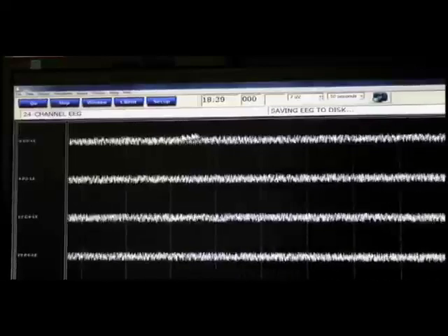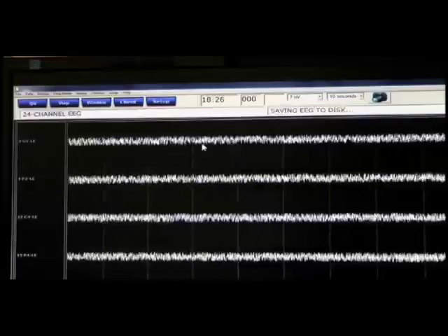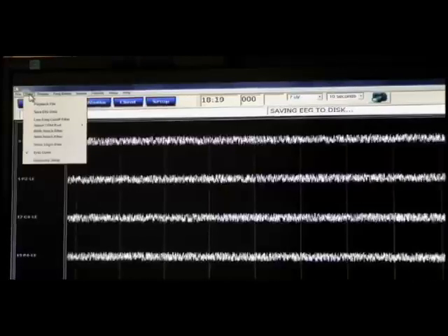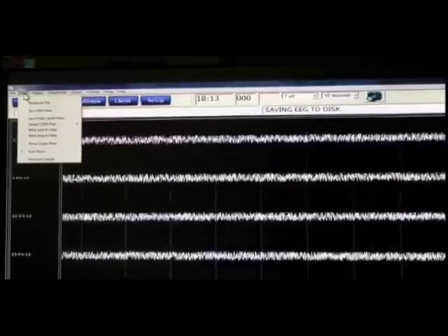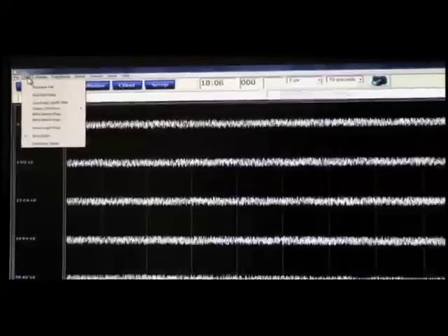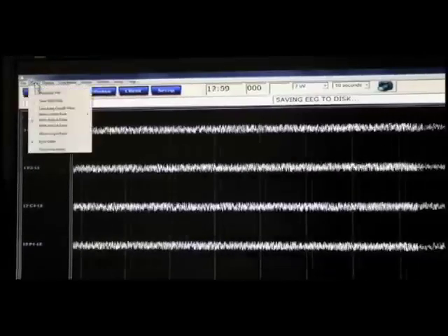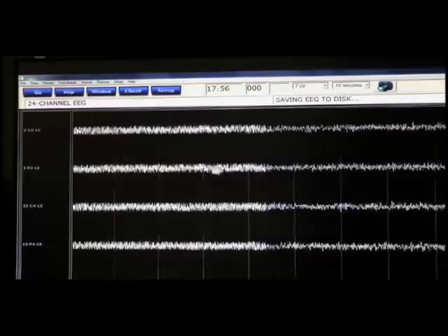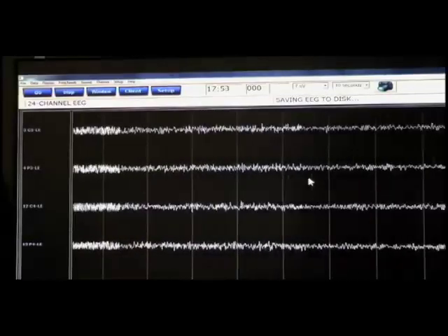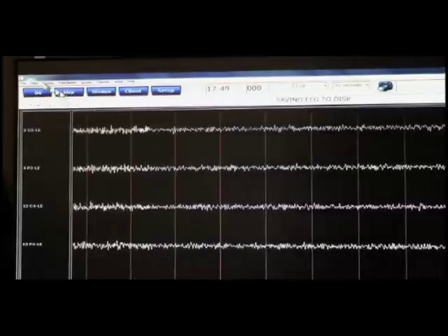When we have a signal like this, it's that typical garbage in, garbage out. So I would want to clean up my electrode placement or find out, is my amplifier too close to the computer? We want to make sure our feet aren't close to an extension cord. Something like that could be causing that kind of noise. But for this exercise, I'm going to put these notch filters on just so we have relatively usable data, okay, for this exercise.